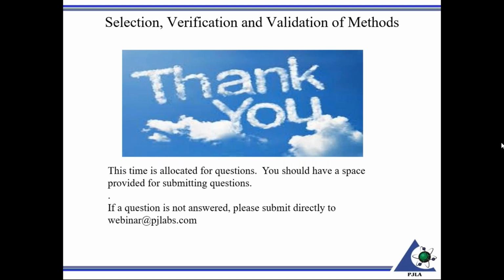particularly if we're going to change your scope of accreditation to reference a different location, because technically once you move, that old location is not under your scope anymore. So you need to let us know. 17025 does not address that specifically, regarding moving. You just have to assure that, even in your testing in the facilities section, you have to document any sort of environmental limitations which you need to operate under.